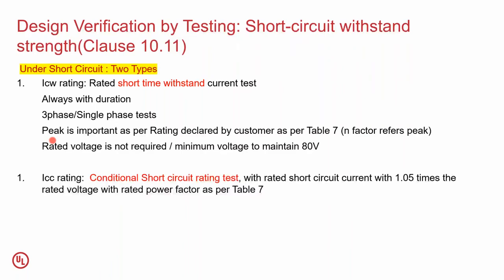This is the difference between the UL standard and IEC standards. Here we are not worried about the rated voltage under the short time withstand current test. Minimum 80 volts is more than sufficient, as long as you get the required current and the peak current under the short time withstand current test. Don't forget this.